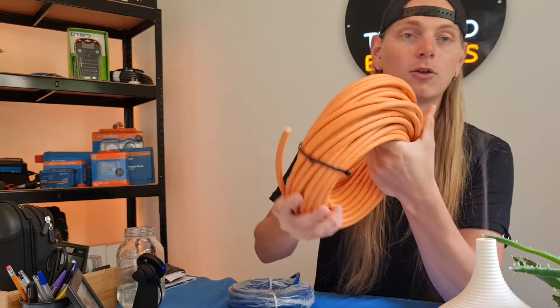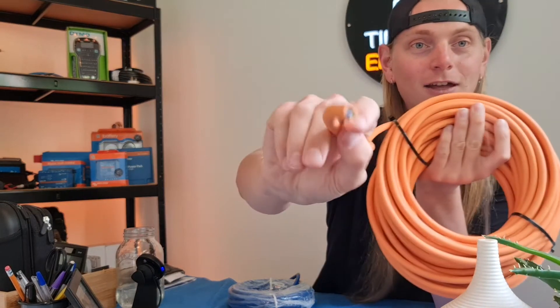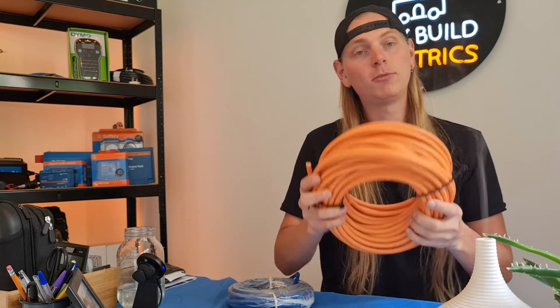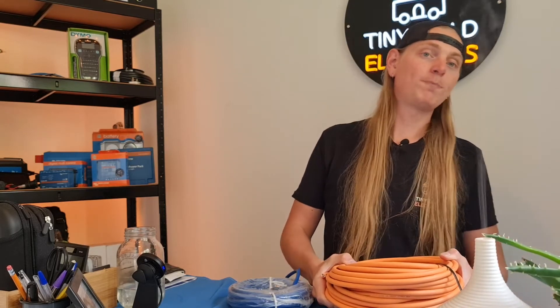You can see we've got a big bundle of delicious orange cable here, à la Tiny Build Electrics. This cable gauge is 2.5 millimetre. As I say, this is required from your shore power inlet up to your consumer unit, whether you have a shore-power-only setup or an inverter-charger.